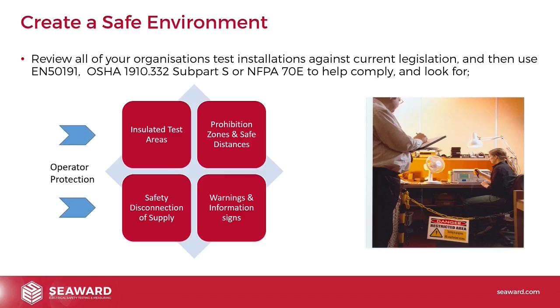So we're going to use insulated test areas and safety disconnection of supply to both lower the chance of a shock and to make sure that if a shock occurs, it is time limited and won't happen for very long. The next thing we'll look at is prohibitions and safe zones and warning and information signs, which are designed to help non-trained personnel be aware of the risks and not be in a situation where they could get a shock.